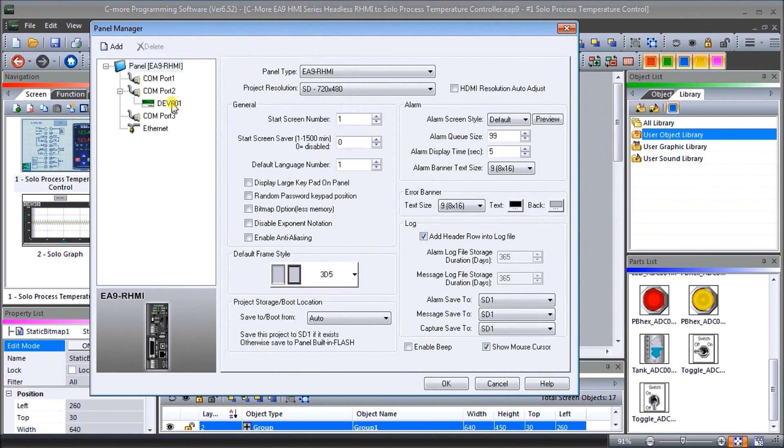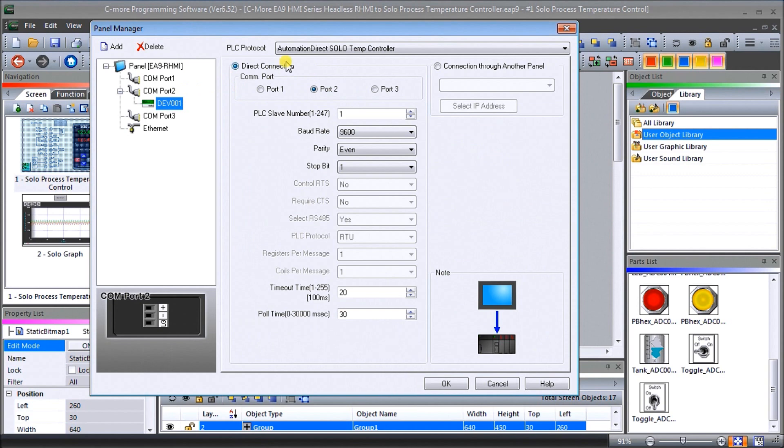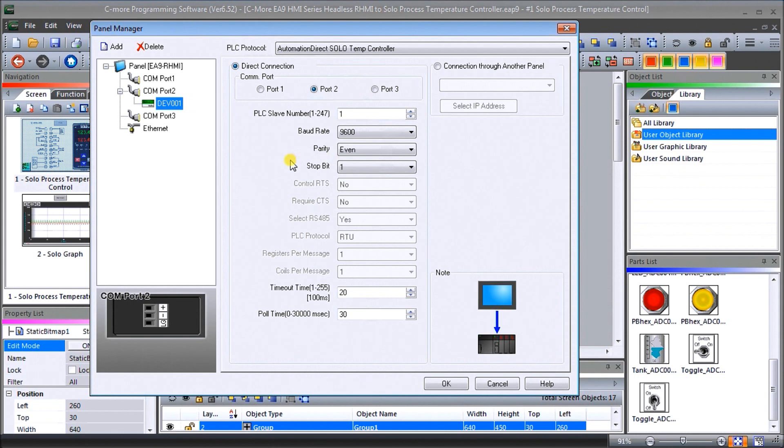Then if we look under the COM port you can see here that our protocol will be the automation direct solo temp controller. It's coming in port number two. The slave number is going to be one, the baud rate and parity and stop bit 9600 even in one. Then we have our timeout so we left as default.